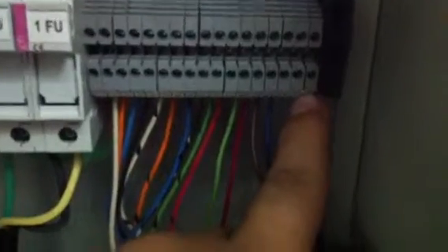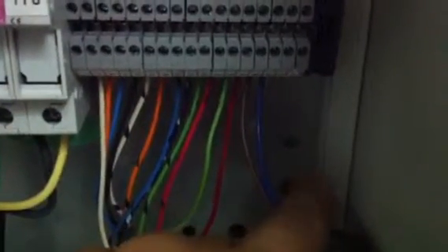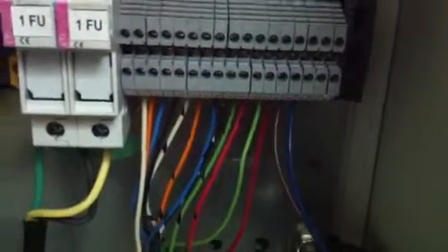Additional to that, we have another set of contacts over here in case you want to interface your system with this one, or by simply using the voltage supply over here, that we usually connect to some kind of magnetic holder for the doors to close or for the hoppers to close when an alarm appears. But that's a safety relay, and that works in conjunction with all the fire alarm sensors and the panel.